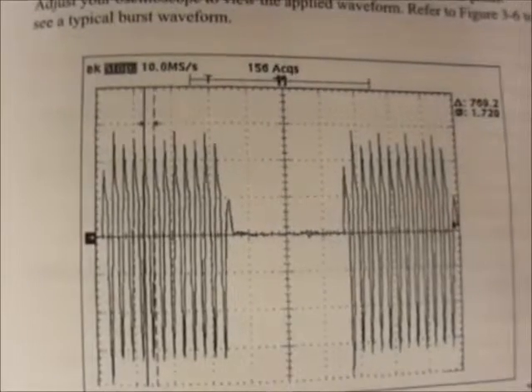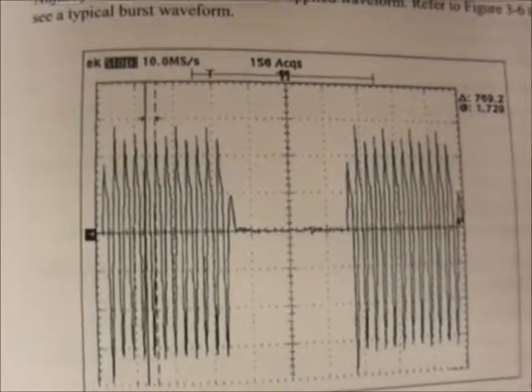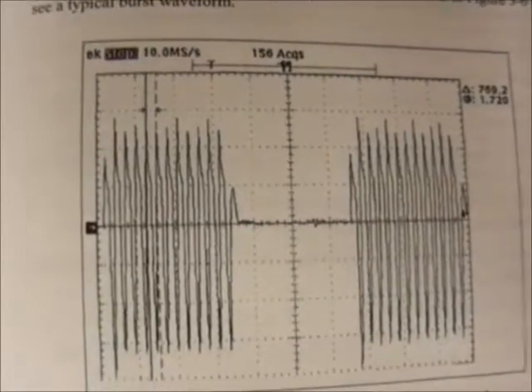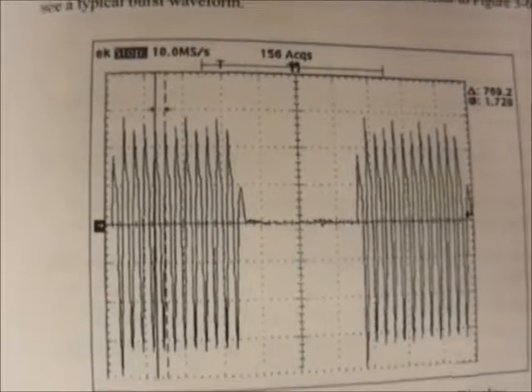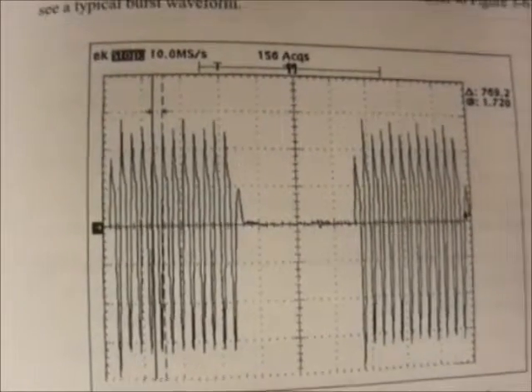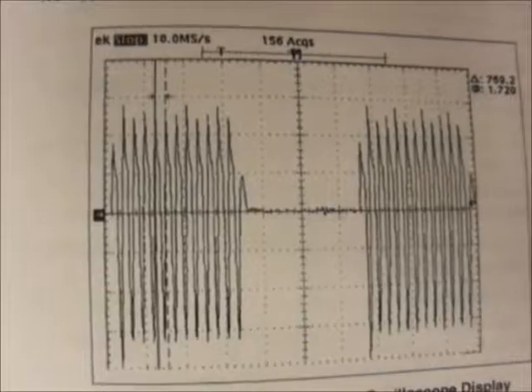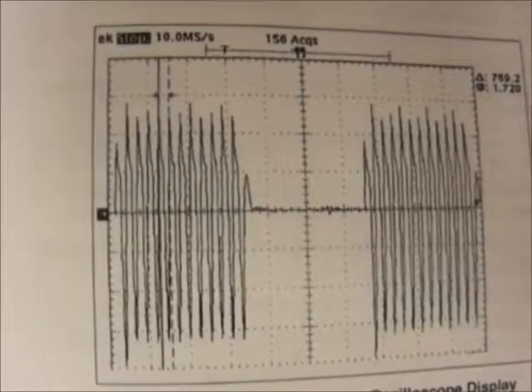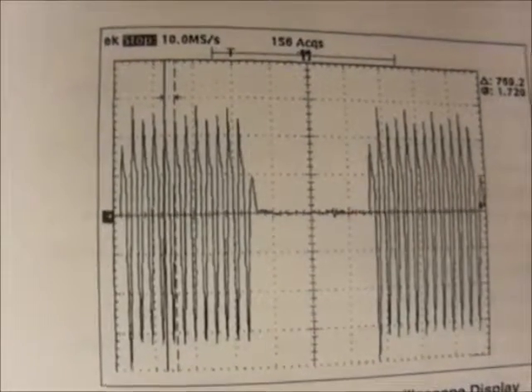Finally, we measure and document high Crest Factor for coag, which is normal, and low Crest Factor for cutting, which is also normal, as well as any distortions or noise found on the higher waveform harmonics.